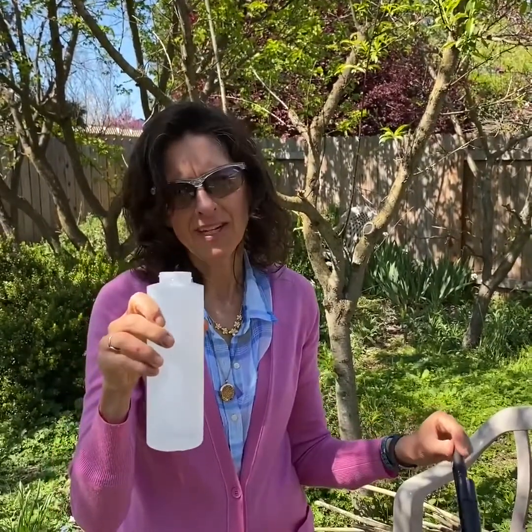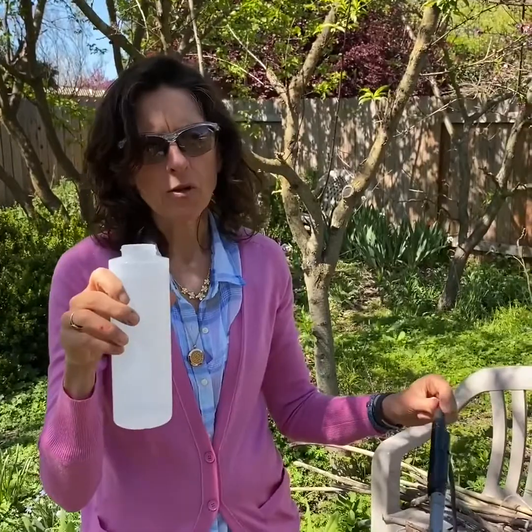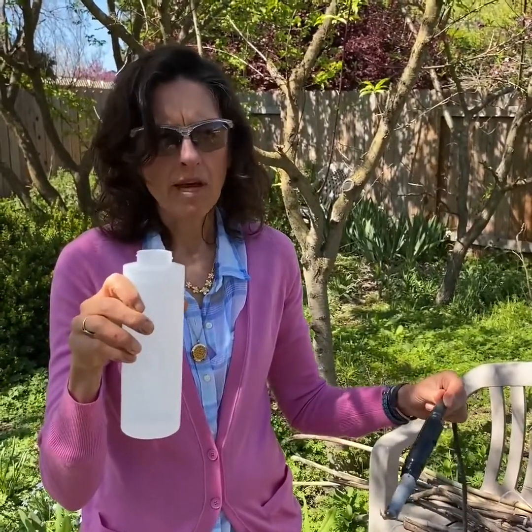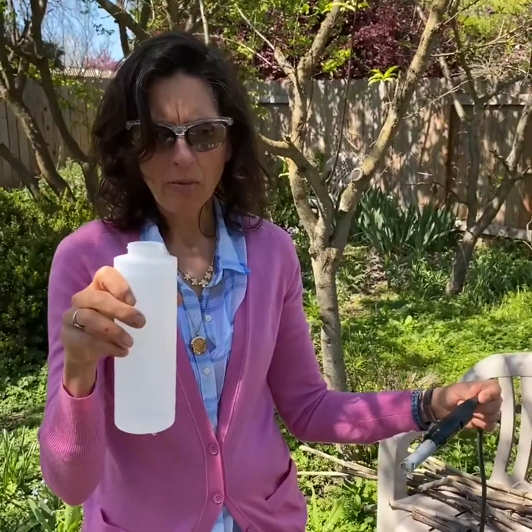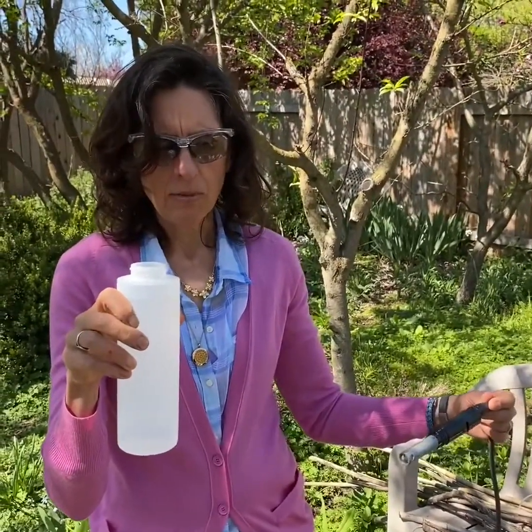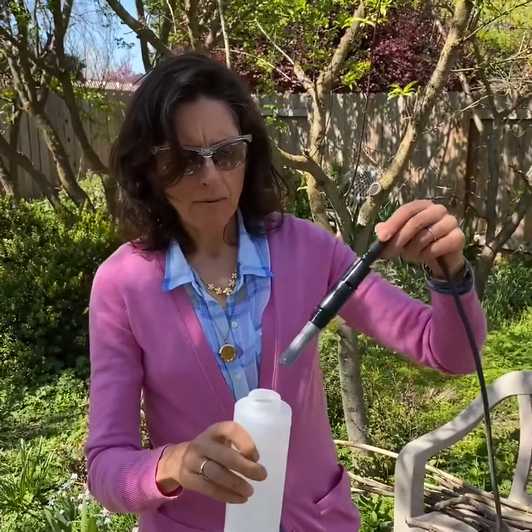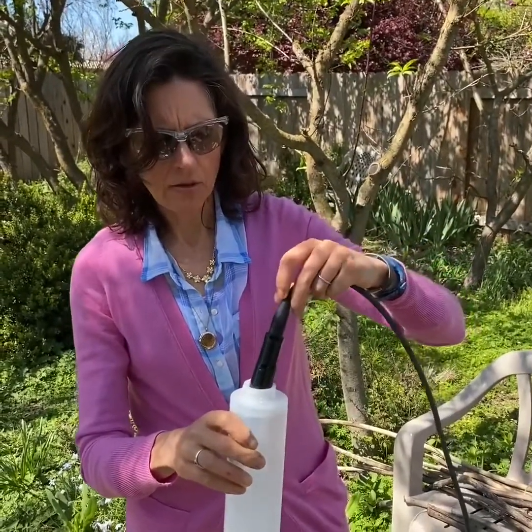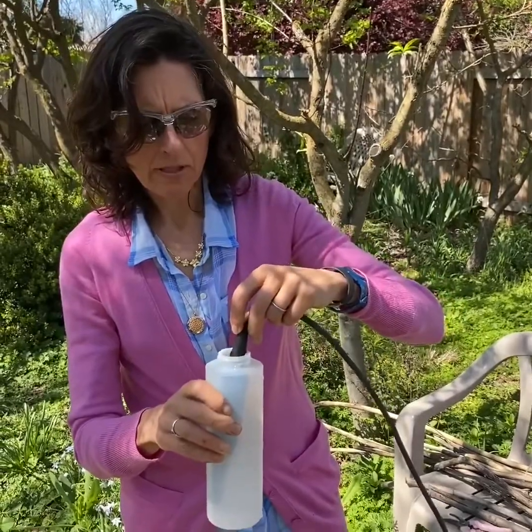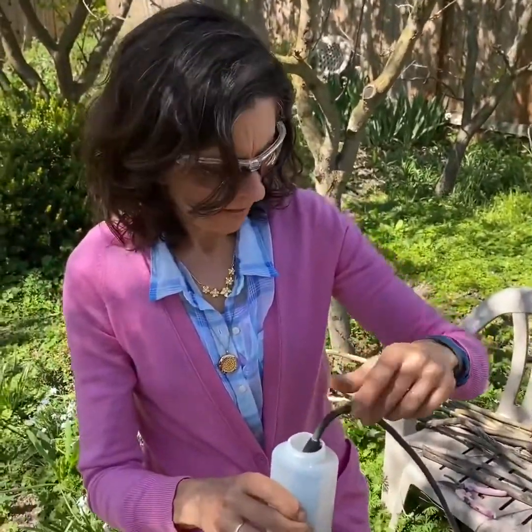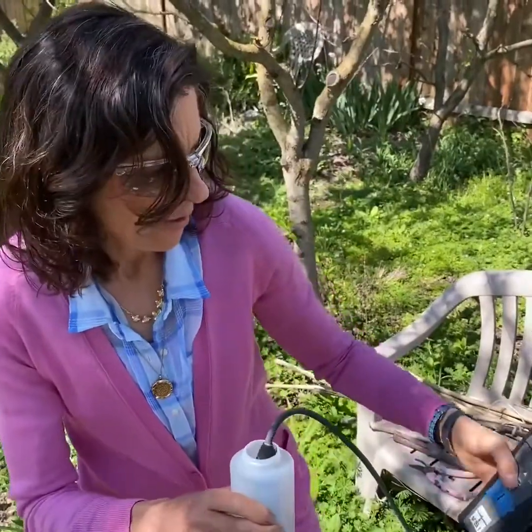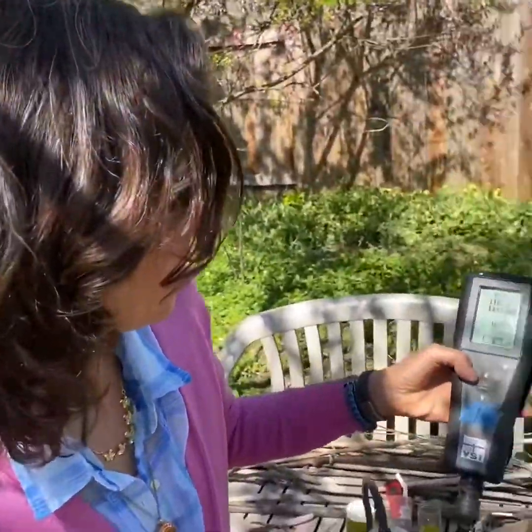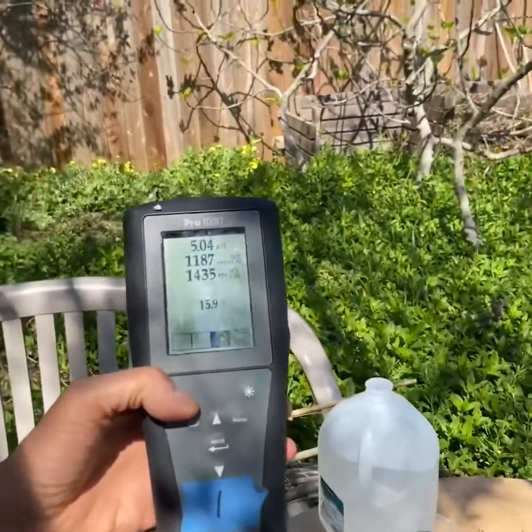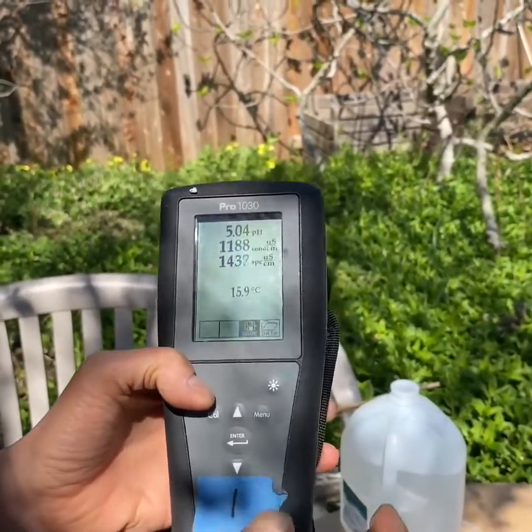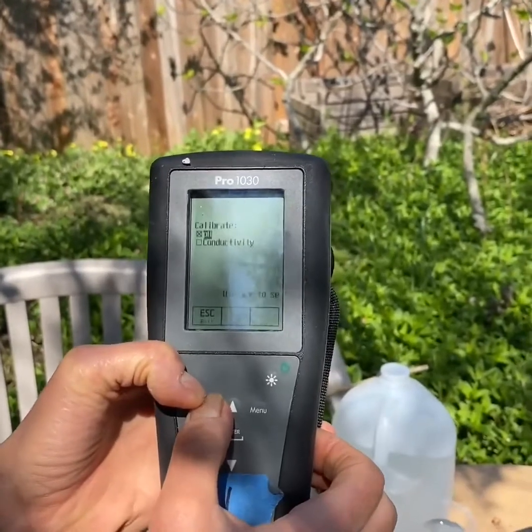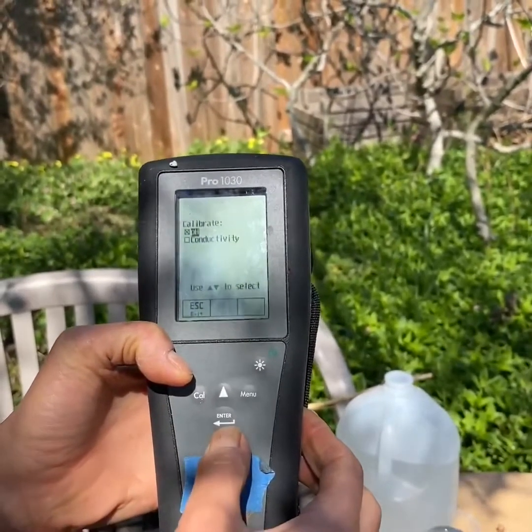Remember, in the pH video we had a rinse solution, so we could just get that one dirty and it wouldn't matter if we had a little water left on our probe, because it's just the rinse solution. So I put it in the rinse solution first, and now I'm going to stick it into the real calibration solution, real bottle, and I'm going to set this in the sun this time. I'll set down my bottle and press and hold CAL, C-A-L, and I'm going to switch it over to conductivity.